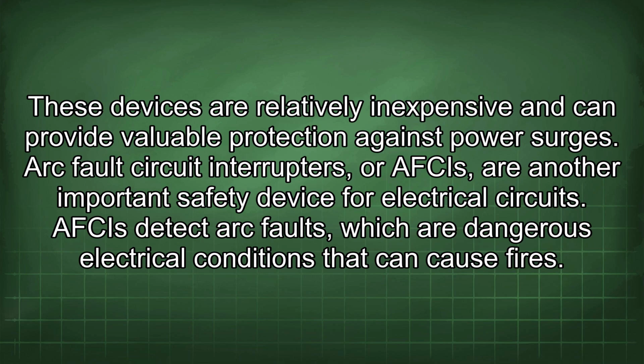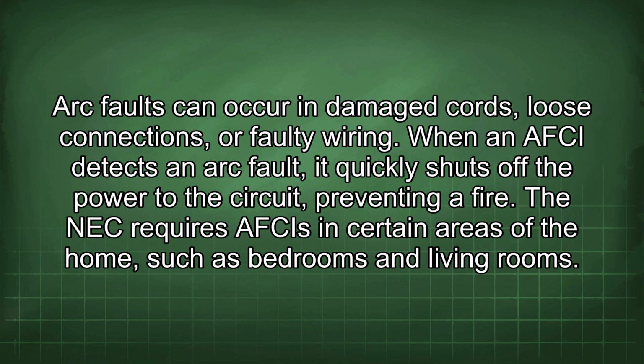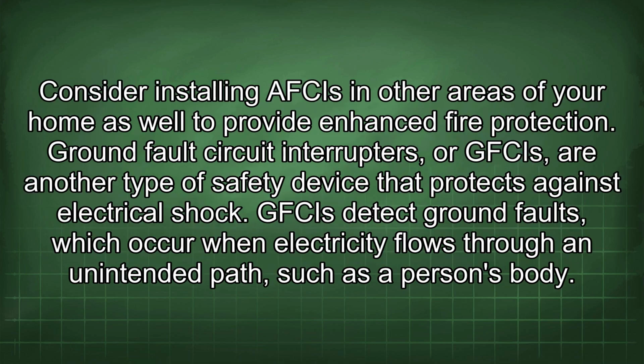Arc fault circuit interrupters, or AFCIs, are another important safety device for electrical circuits. AFCIs detect arc faults, which are dangerous electrical conditions that can cause fires. Arc faults can occur in damaged cords, loose connections, or faulty wiring. When an AFCI detects an arc fault, it quickly shuts off the power to the circuit, preventing a fire. The NEC requires AFCIs in certain areas of the home, such as bedrooms and living rooms. Consider installing AFCIs in other areas of your home as well to provide enhanced fire protection.